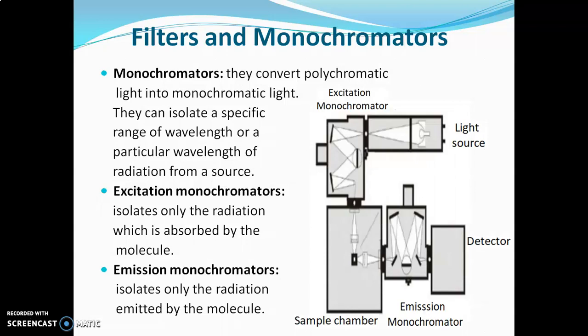Monochromators convert polychromatic light into monochromatic light. They can isolate a specific range of wavelengths or a particular wavelength from a source. The excitation monochromator isolates only the radiation absorbed by the molecule, while the emission monochromator isolates only the radiation emitted by the molecule. Monochromators are more sensitive and more effective than filters, and are used in expensive instruments like the spectrofluorometer.